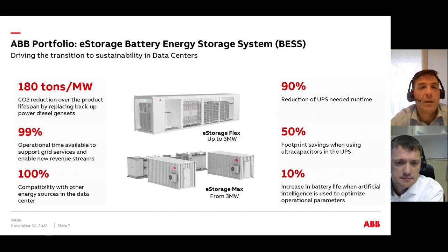This is going to generate an additional revenue stream. The battery energy storage is 100% compatible with other energy sources in the data center, such as PV and wind or fuel cells, diesel gensets, the grid. All the energy mix is compatible with the BESS. The BESS is much faster than that genset, so we can reduce by 90% the UPS backup needed time.